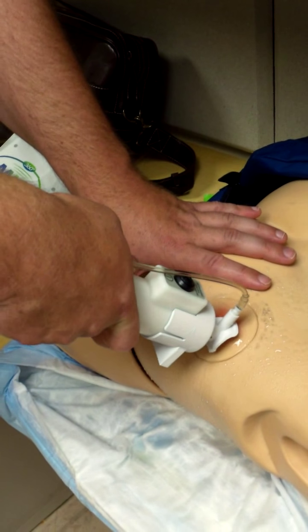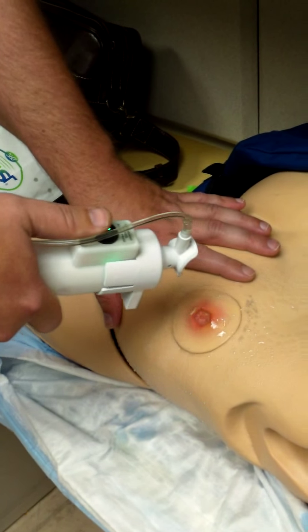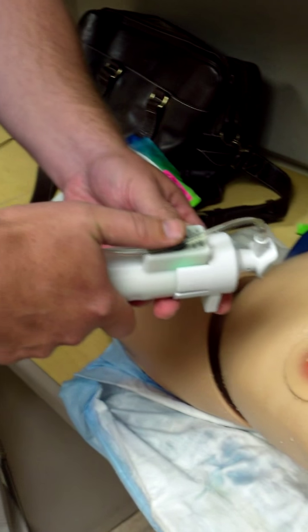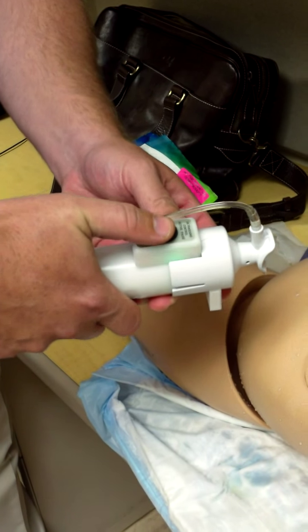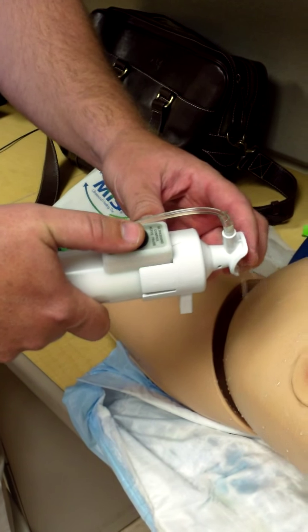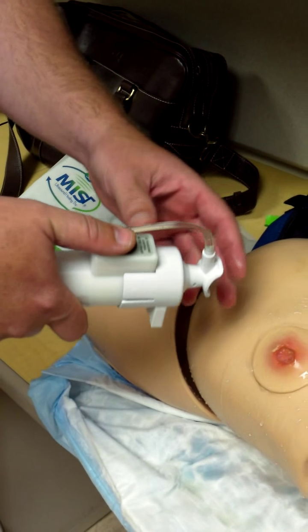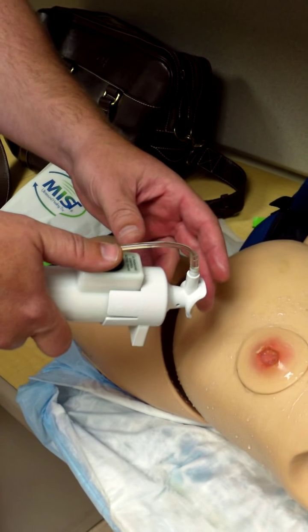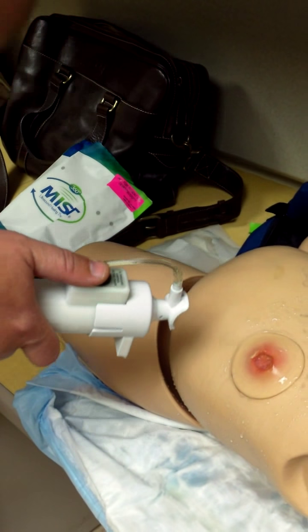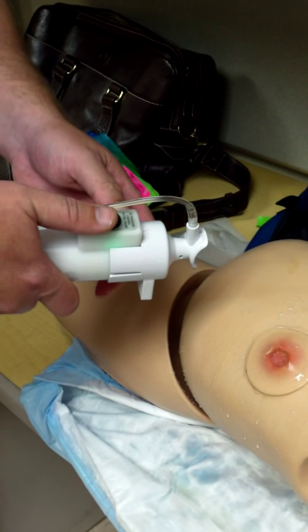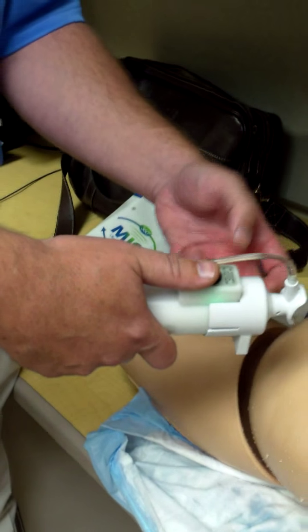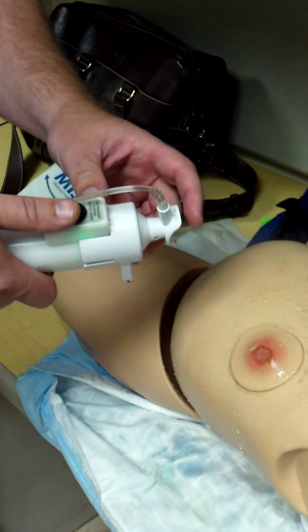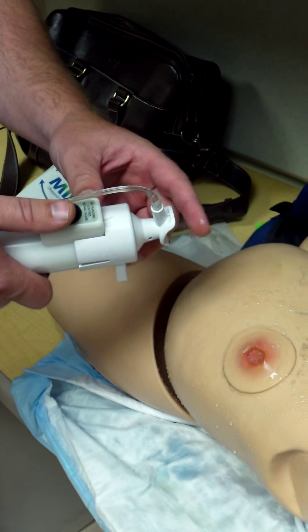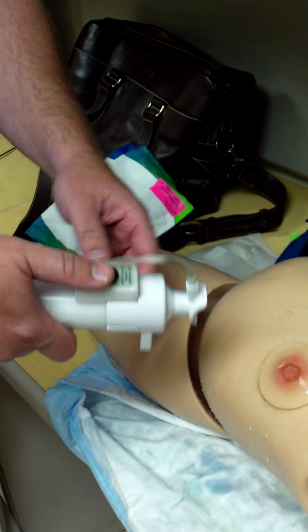The only other thing that I'll show you is that sometimes you may get a frequency slip, and basically all that is something that's blocking the transducer tip. So if I put that tip in water and tried to turn it on, it would say frequency slip on the machine. So if you ever get that, just turn the machine off and turn it back on. It's just basically saying something's blocking the transducer tip.